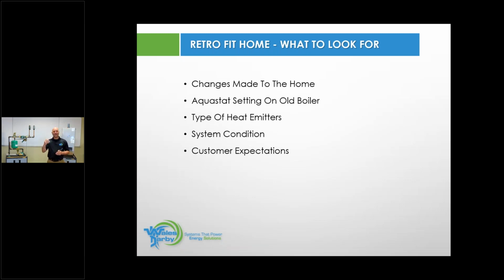So back to that heat loss calculation, you have to do a heat load calculation on it. It's critically important to make sure you're sizing this right. And then after you do the heat load calculation, it's always important to understand what changes have been made to the home. Have they made the home more energy efficient? So the heat load calculation will do that for you. So you could be looking at a 150,000 BTU boiler. It's in the basement currently, but they've sided, they've insulated, they put new windows in, they've put new doors in, and now the envelope heat load calculation may be 90,000 BTU. So very important to pay attention to that.